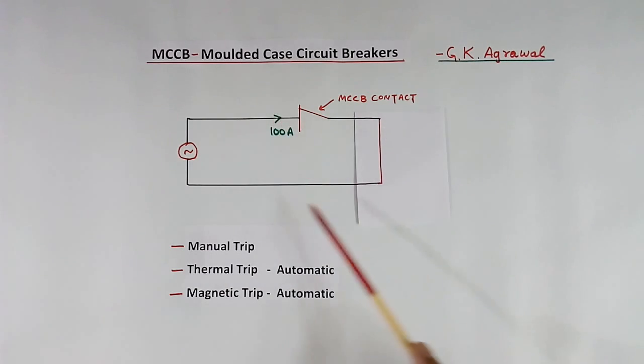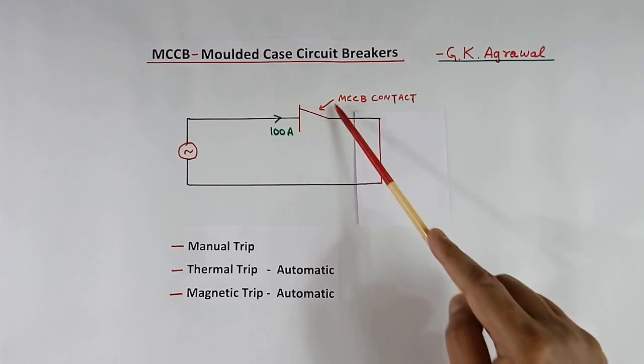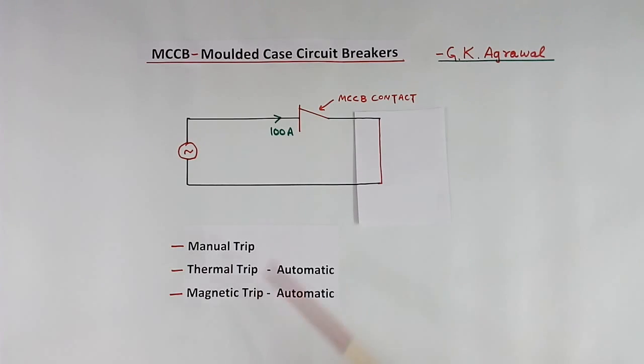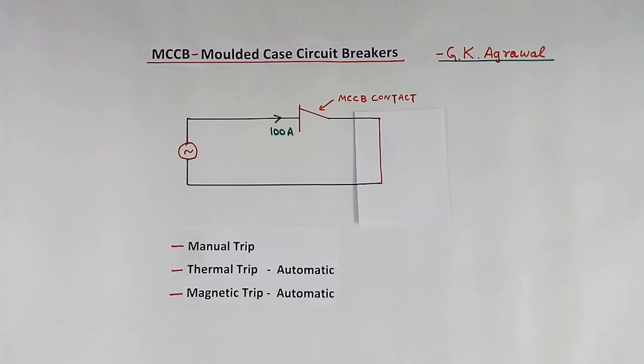The second possibility is that instead of overload, it becomes a short circuit. In this case, very heavy current will flow, and the MCCB magnetic trip unit will trip and this contact will open.